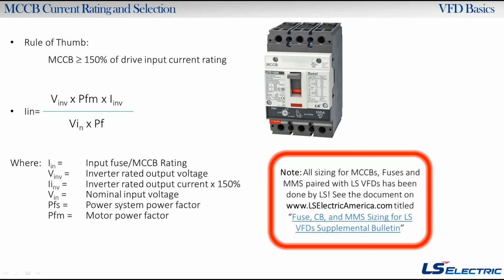I'd also like to mention that we have all of the LS products pre-selected and pre-sized for you. We have documents on our website, which we just recently changed, for those of you who haven't figured it out yet. The new website is www.lselectricamerica.com. All of the downloads should still be there. We have a fuse, circuit breaker, and MMS sizing guide, MMS being a manual motor starter. So you could say I have a 10 horsepower H100 drive, and it'll tell you, use this fuse, or you could use this MMS, or you could use this circuit breaker. The circuit breakers and MMSs, the products that we make, have actually been UL tested with the drive. So it's a good selection tool to use, because we tested it all out.